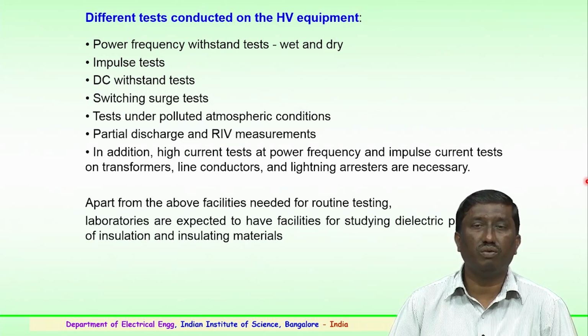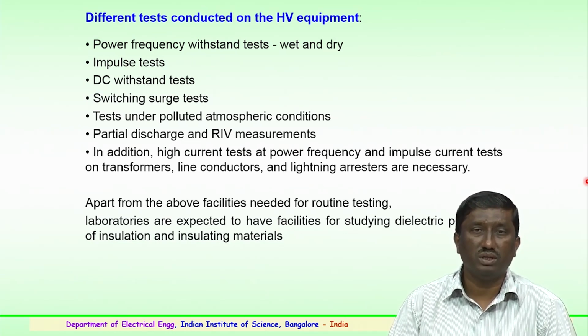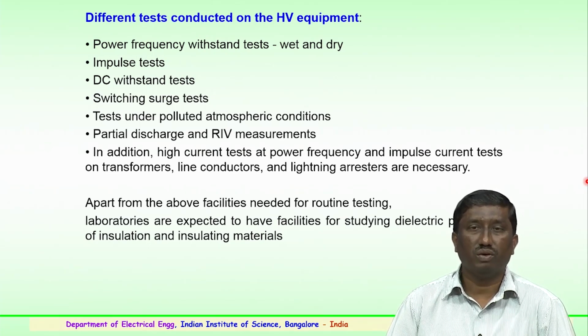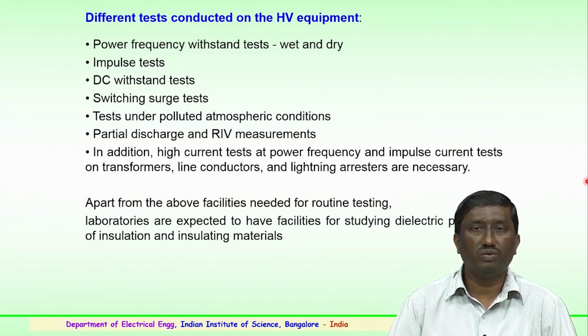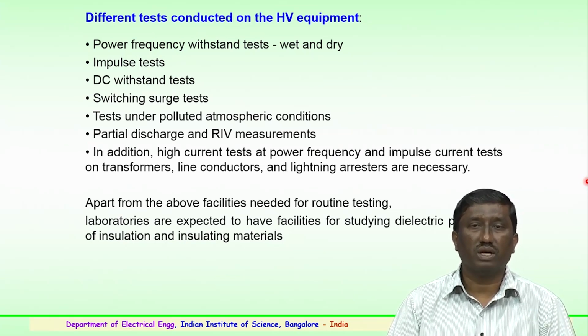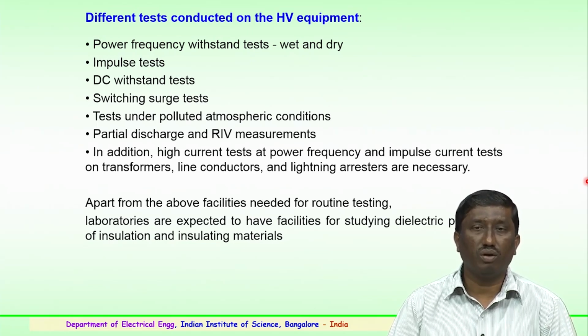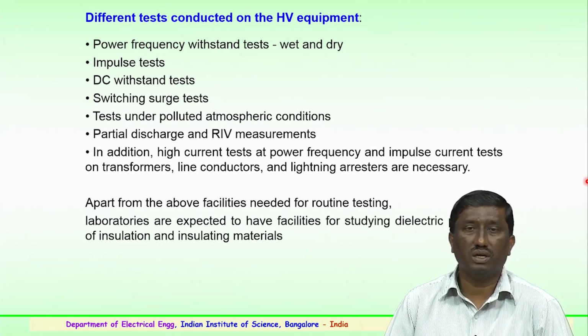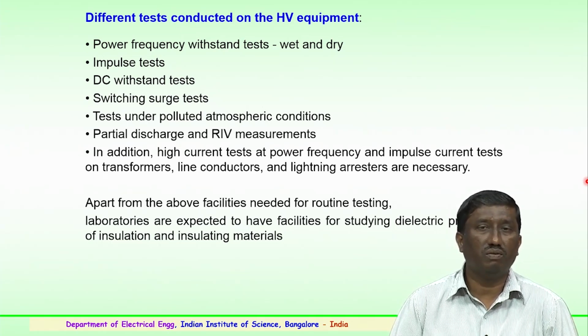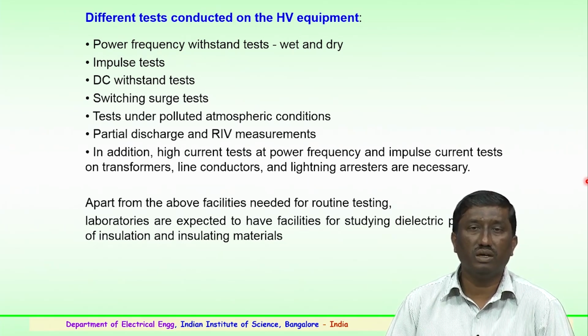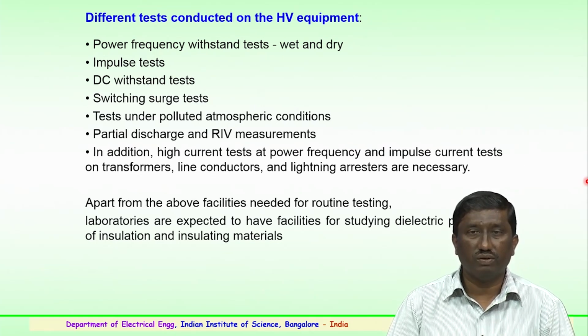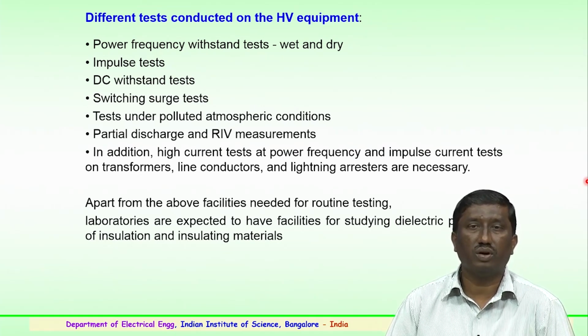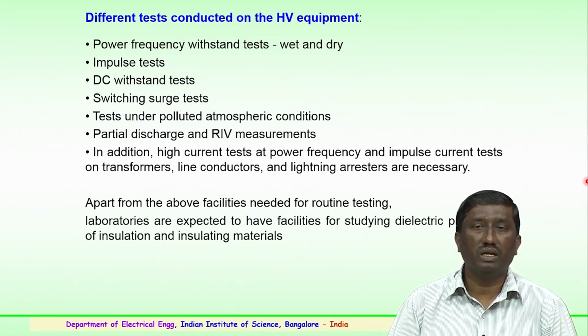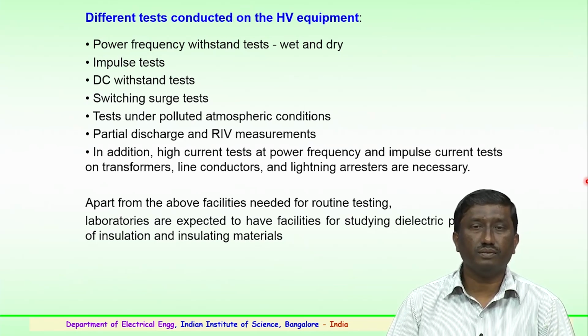Then radio interference voltage measurements, this is a very important measurement which is carried out in the high voltage laboratory for various high voltage equipments. It could be for insulator strings, the line hardware, the conductor, the transformer or many equipments where this test is important and needs to be done at the laboratory. In addition, high current tests at power frequency and impulse current tests on transformers, line conductors and lightning arresters are equally necessary.